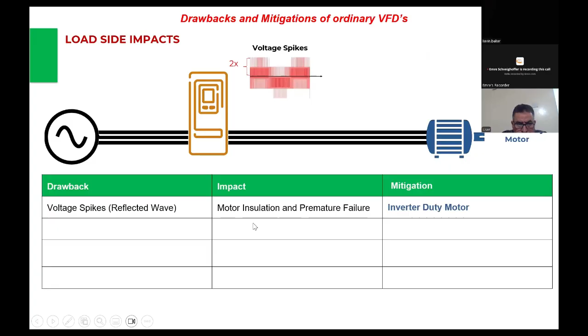So a common mode choke gets put in for a lot of people. Some will buy a reactor, or spend more for a dv/dt filter, or spend the most for a sine wave filter. That can also go in line on the load side of the VFD. You'll also have to buy an inverter duty motor, what we call a NEMA MG1 Part 31 motor. All of this is because we're trying to make this square wave look like a sine wave to the motor. This is just a summary of all the mitigation we do against the common problems on the back end of your VFD.